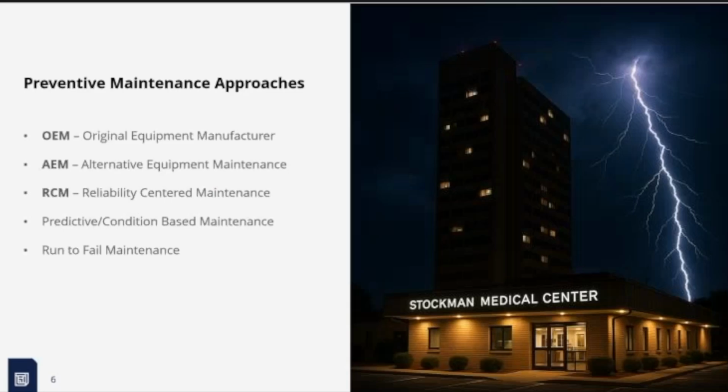What is AEM? And we're going to define a couple of different preventive maintenance approaches when we talk about that. So OEM, we'll start with that one. Original equipment manufacturer. That is the book that comes with your equipment. You're supposed to do everything in that guide, the manual, to maintain that piece of equipment. And what that means, to the letter of the law, is you're doing that.